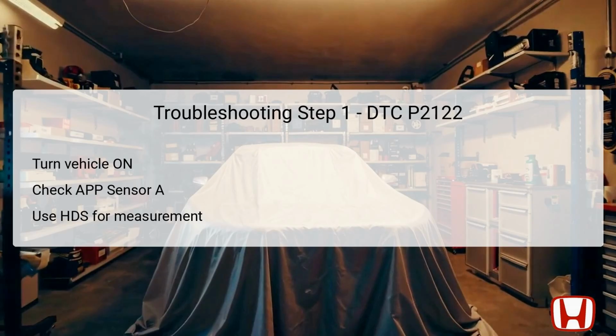If the current conditions match the specified threshold, the failure can be considered confirmed, allowing you to proceed to the next troubleshooting step. However, if the signal does not align with the threshold, it may indicate an intermittent failure, prompting the need to check for poor electrical connections or loose terminals, either at the APP sensor or the PCM.